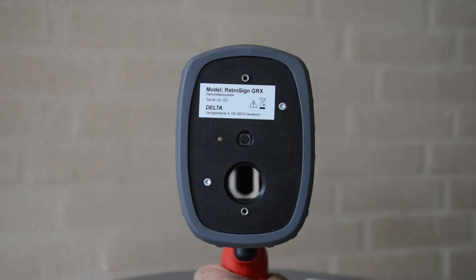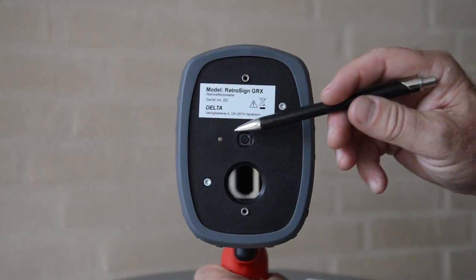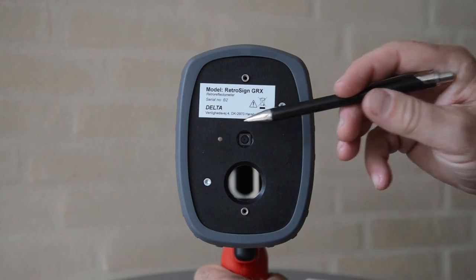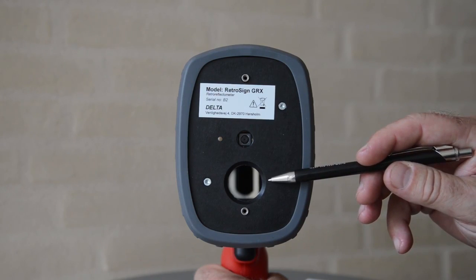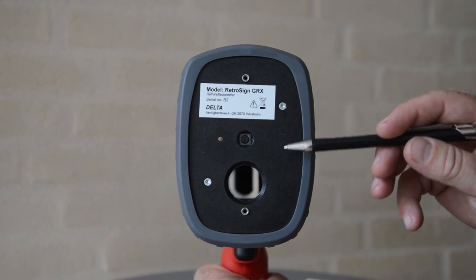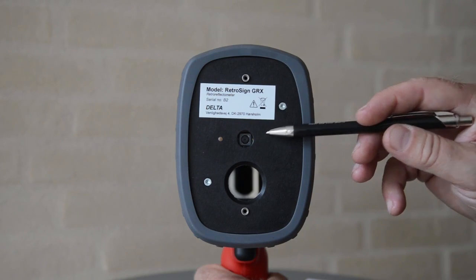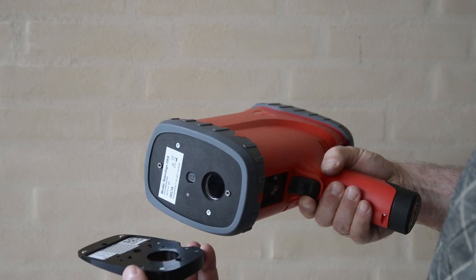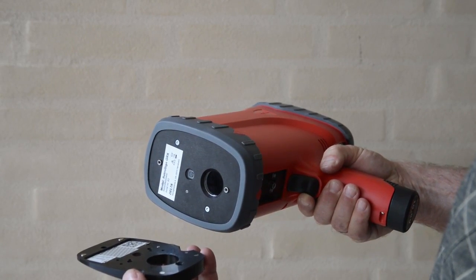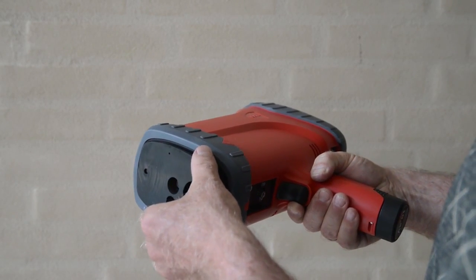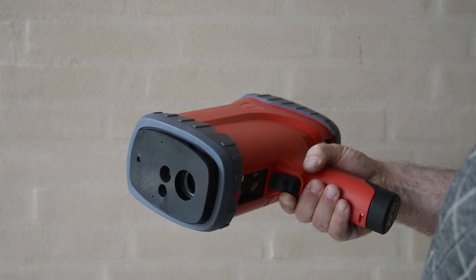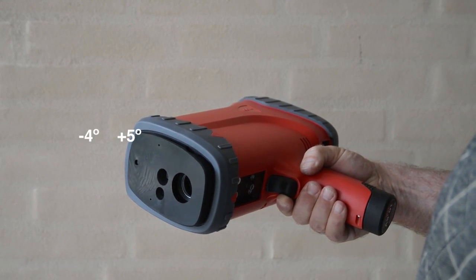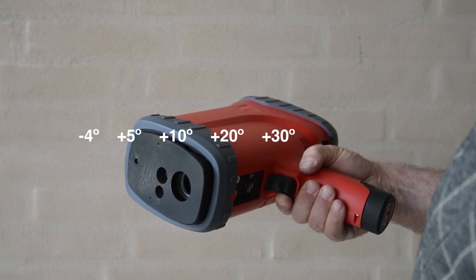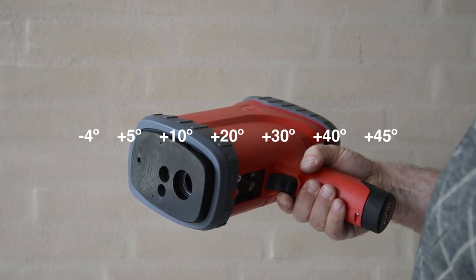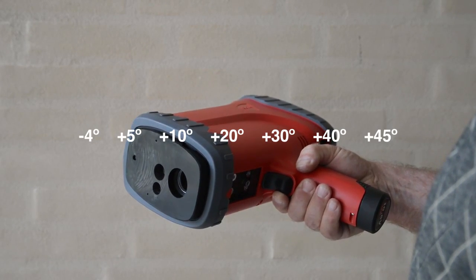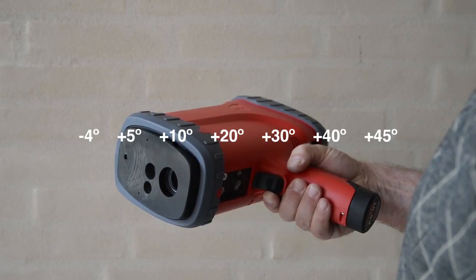At the front of the instrument, we have the light source based on LED light, the measurement sensor for reflection measurement and color recognition, and the digital camera for photo and code scanning. Over the instrument front, an angle adapter for entrance angle is mounted. The available entrance angle adapters are -4 degrees, +5 degrees, +10, +20, +30, +40, and +45 degrees, of which the first 2 are standard angles for ASTM and CEN sign geometries.